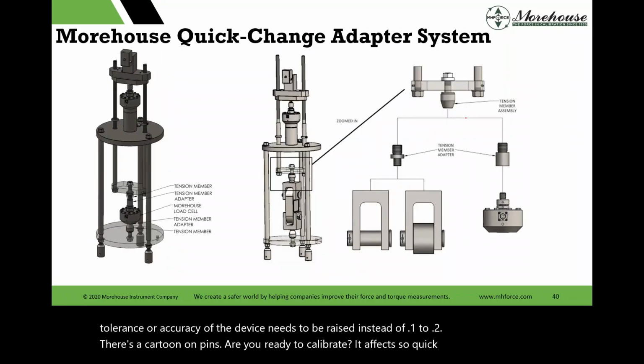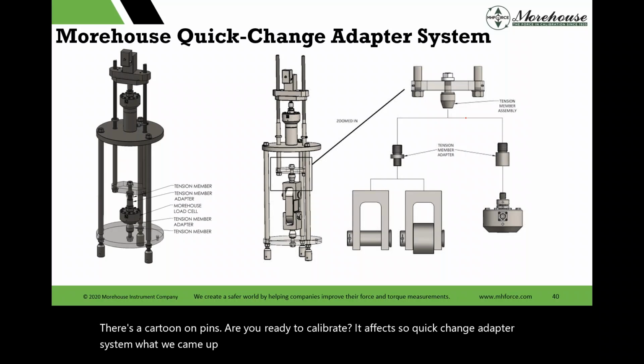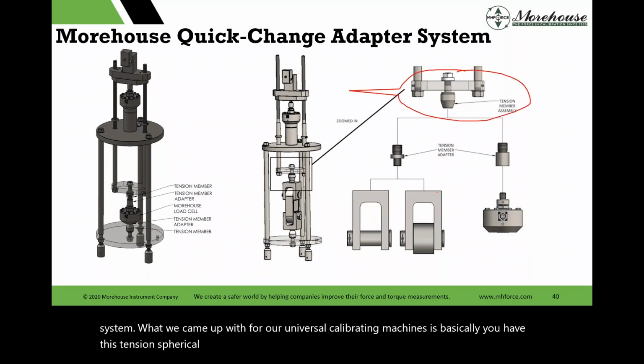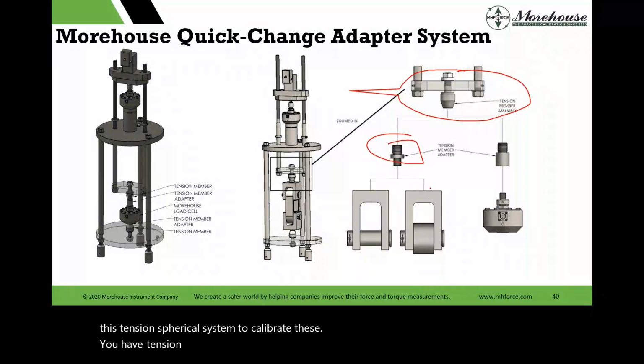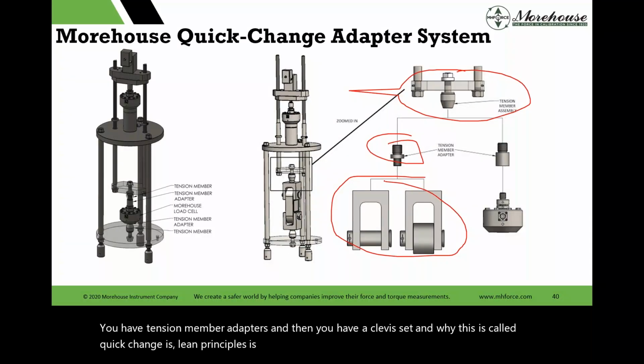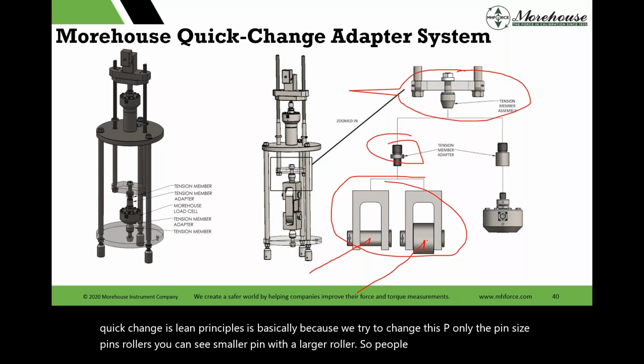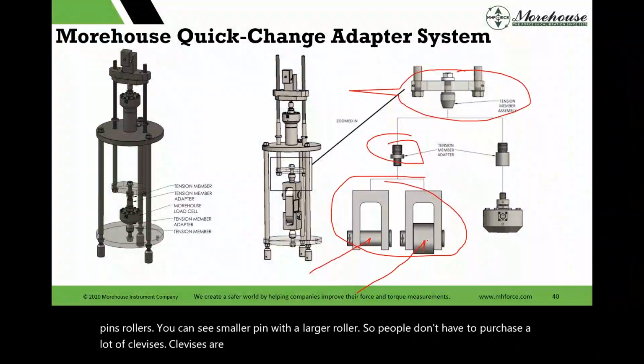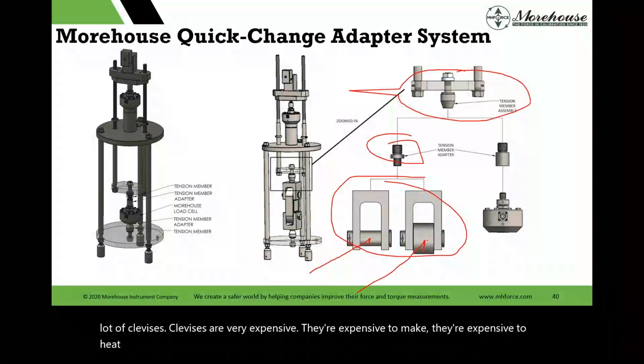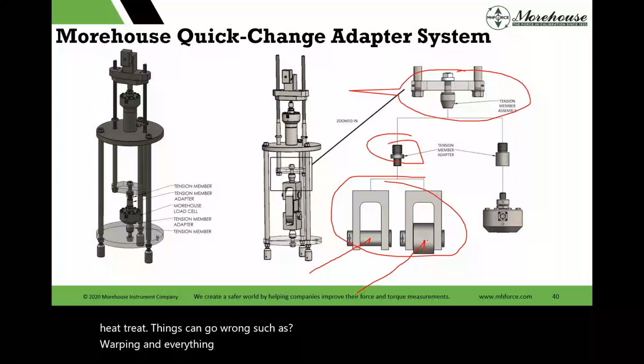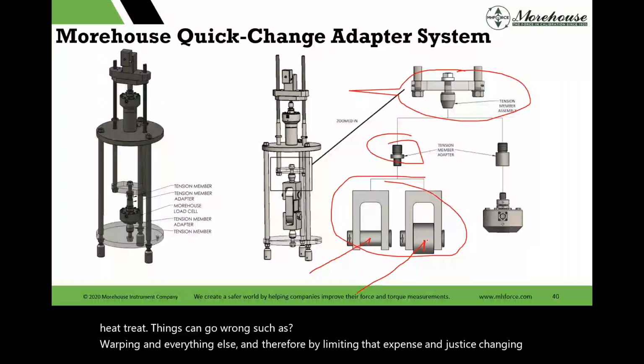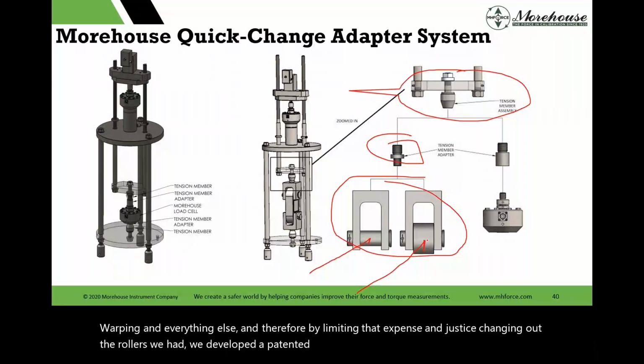So quick change adapter system, what we came up with for our universal calibrating machines, is basically you have this tension spherical system to calibrate these. You have tension member adapters, and then you have a clevis set. And why this is called quick change, this lean principles, is basically because we try to change only this piece, the pin size, pins, rollers. You can see a smaller pin with a larger roller, so people don't have to purchase a lot of clevises. Clevises are very expensive. They're expensive to make. They're expensive to heat treat. Things can go wrong, such as warping and everything else. And therefore, by limiting that expense and just changing out the rollers, we developed a patented system for calibrating these tension links.